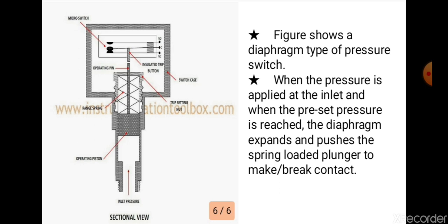In the pressure switch figure, inlet pressure acts on an operating piston or diaphragm region. The diaphragm drives the main shaft, which controls the open and close connections at the terminals — normally open and normally closed. The center portion is normally closed by default. Hydraulic pressure moves the diaphragm and main shaft to switch the contacts.